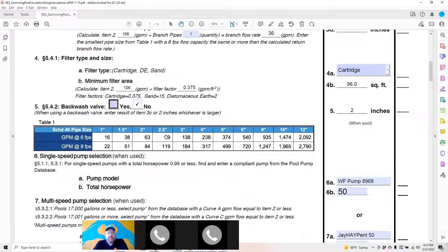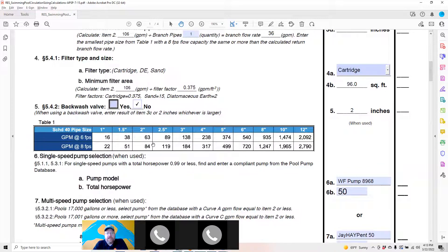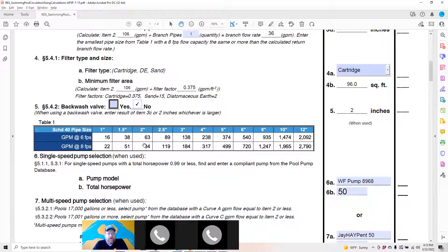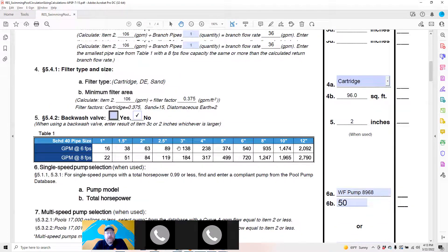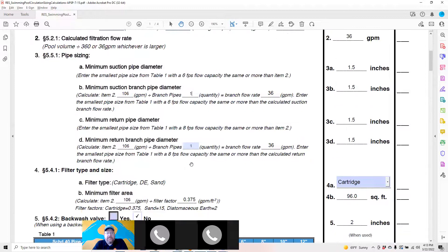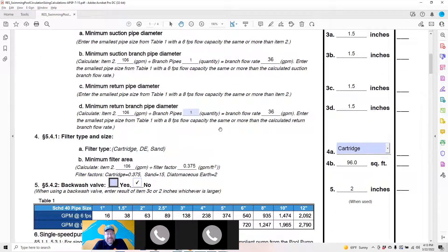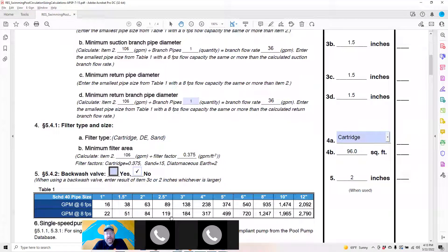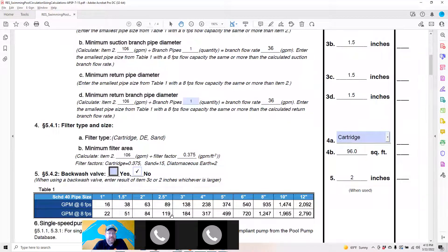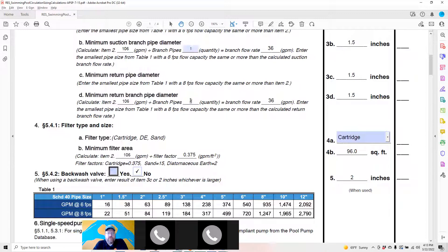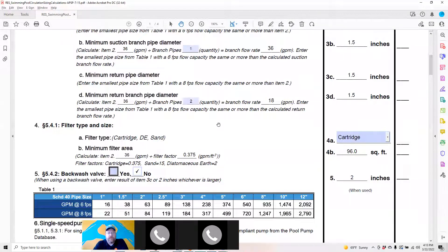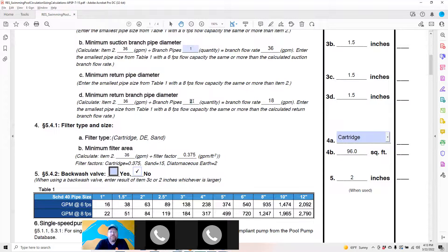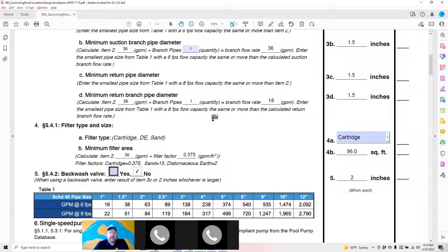If you need two of those in your suction side, we'll put two here. If you only need one, leave it as one. Same on the return side. If you're returning on two inch pipes but the pump is going to move it faster than 84 GPM, you'll either need bigger pipes or more of those two inchers. If that is the case and you have sized two and a half and it's still not enough, then you can add an additional branch line and put a two here.